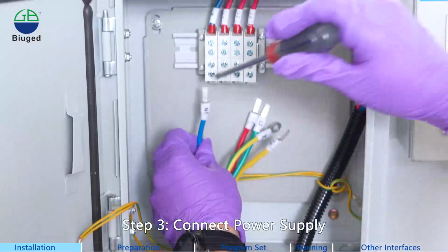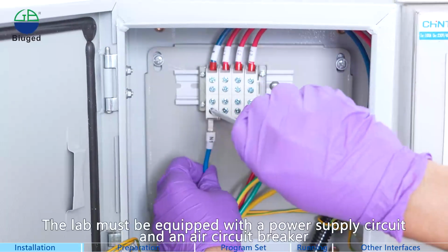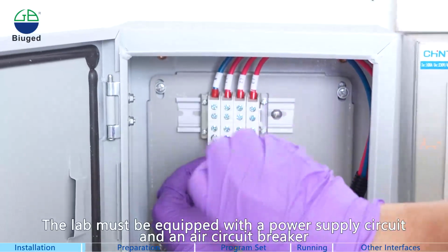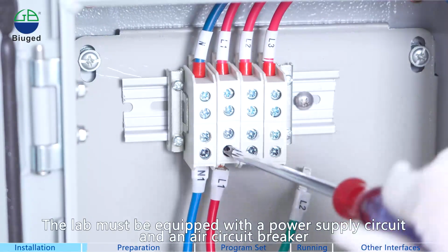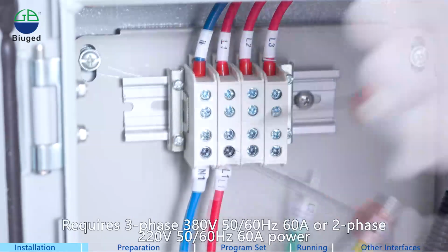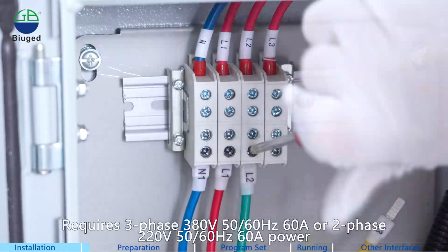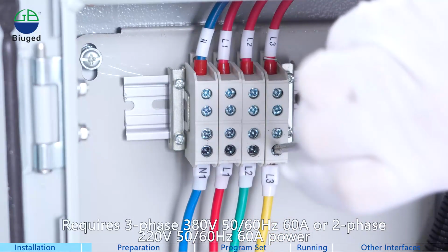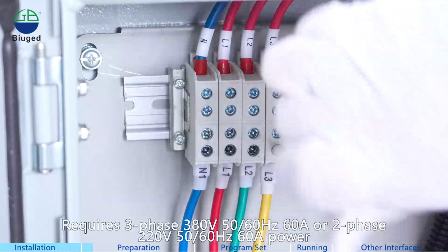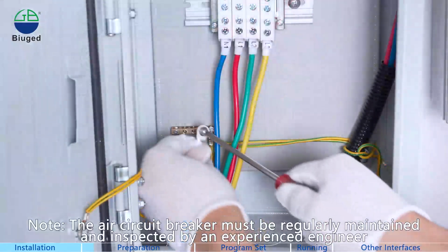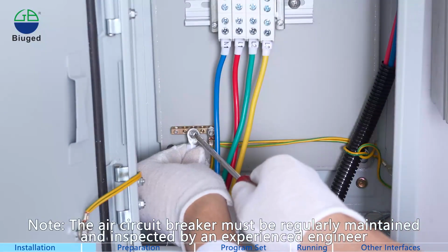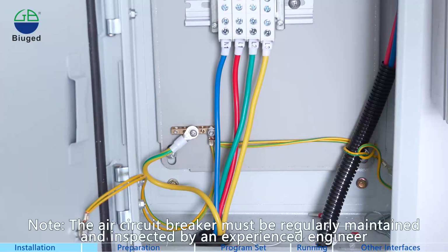Step 3. Connect power supply. The lab must be equipped with a power supply circuit and an air circuit breaker. Requires 3-phase 380V 50/60 Hz 60A or 2-phase 220V 50/60 Hz 60A power. Note: the air circuit breaker must be regularly maintained and inspected by an experienced engineer.